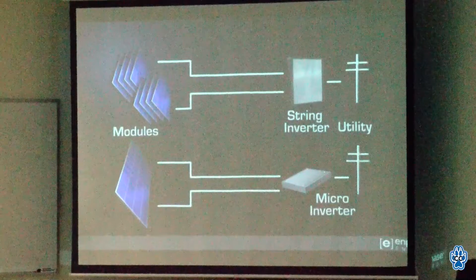Welcome to a presentation of PV fire safety. What you are about to see is a demonstration of the risk of arc faults inherent within two inverter technologies. In this demonstration, we have a meter, a scope, and a gap to simulate a wiring fault. The experiment will begin with no gap. The rods will then be slowly pulled apart, simulating an arc gap from a wiring fault, such as a loose connection. In both cases, inverters are exporting power from the solar modules to the utility grid.